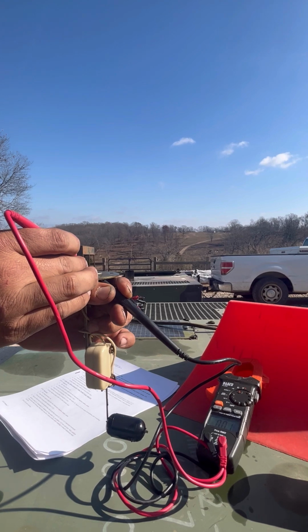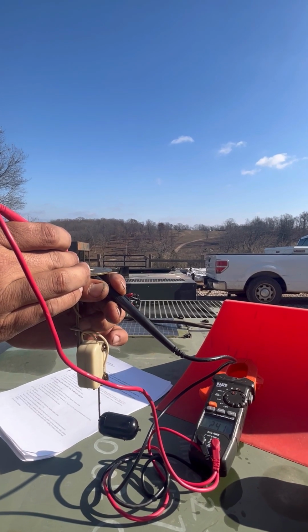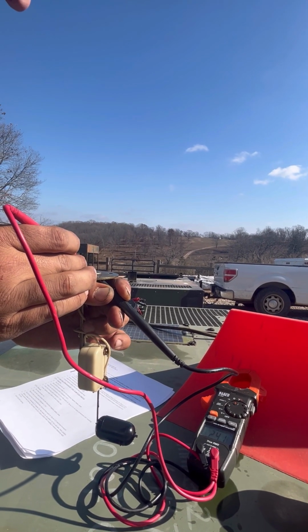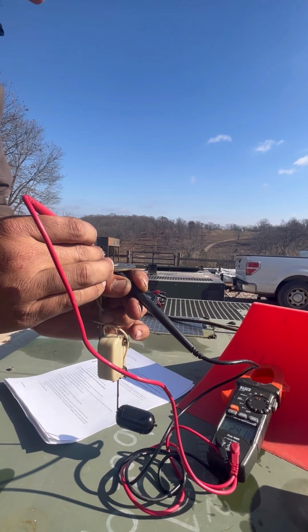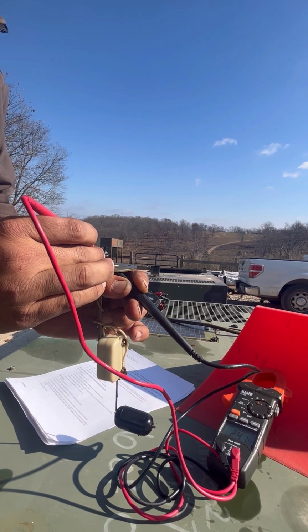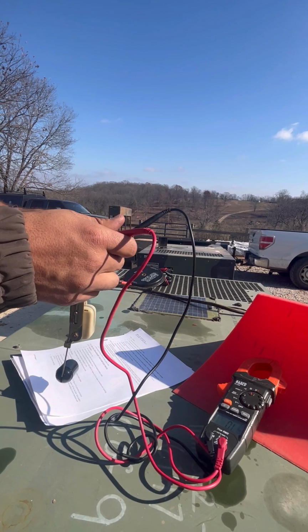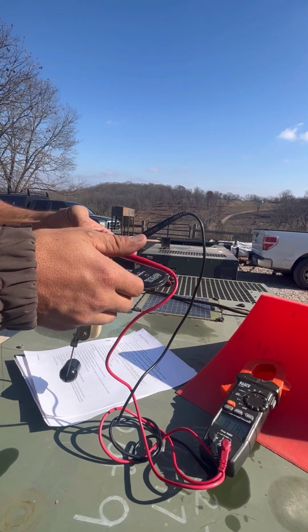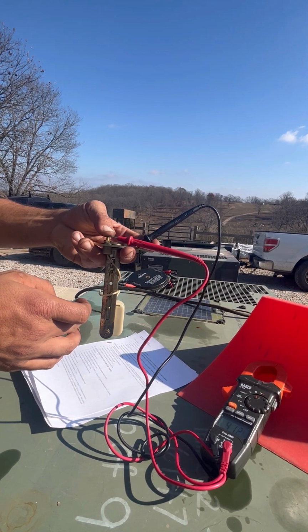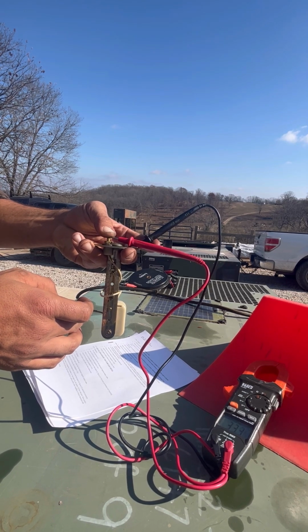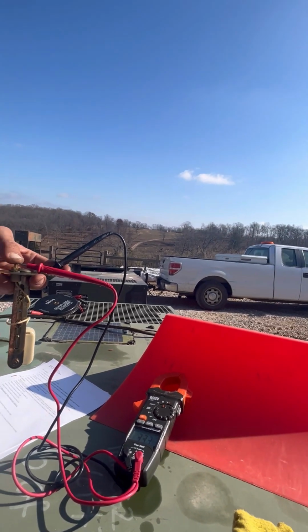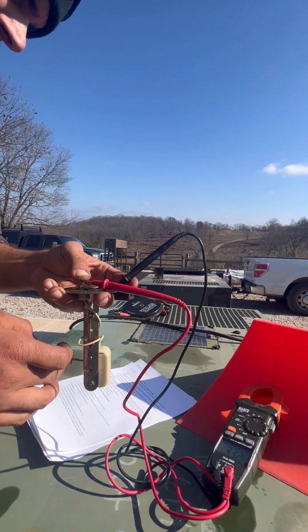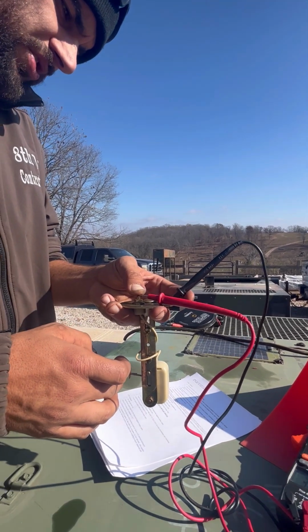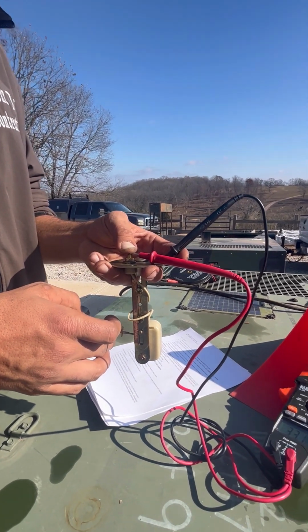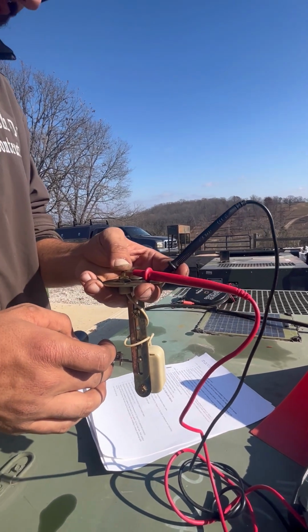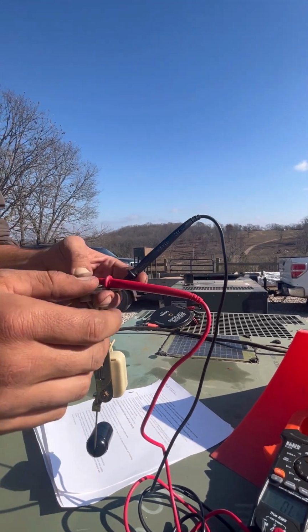And so we are reading 241 ohms, which is almost dead center in between those numbers. 241. Okay, move it up to the full position, and we're reading 33.2 ohms, and that falls again within range of the proper specs. So I'm going to go ahead and reinstall this. This is not our culprit.